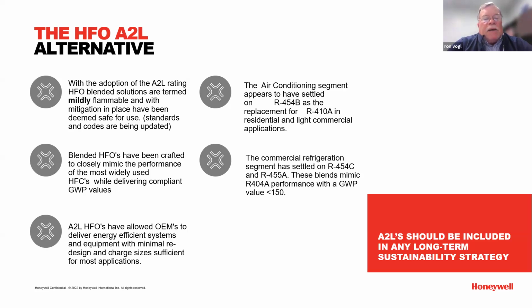So bottom line, it's pretty easy for manufacturers of equipment to move into this stuff. And from a technician standpoint and the rest of it, you'll see as we move forward here, very similar pressures, temperatures, superheat, subcooling, all the same things we're used to doing. With A2Ls, there's a little bit more emphasis on safety going forward because it is mildly flammable, but it can all be handled in a very safe manner. It's the next step in refrigerants.